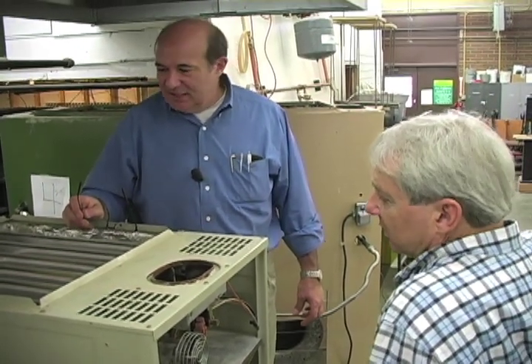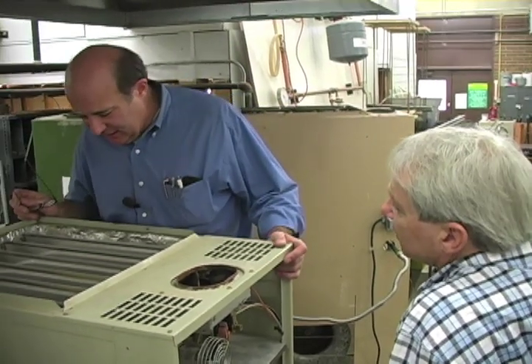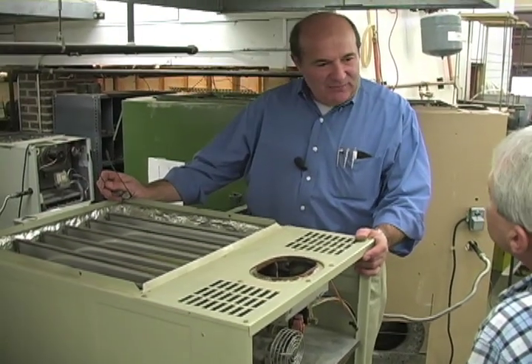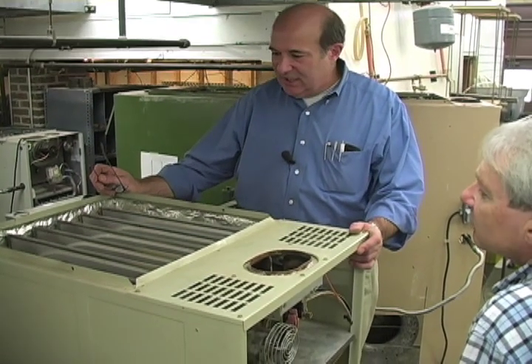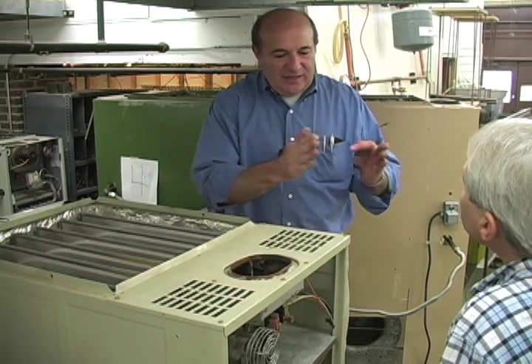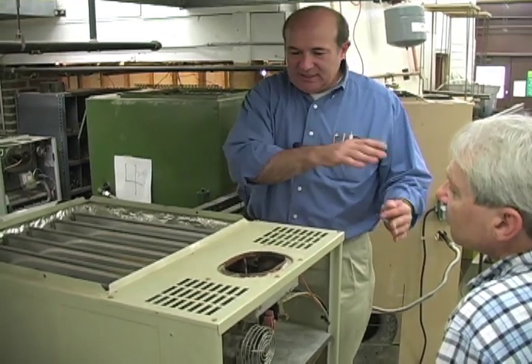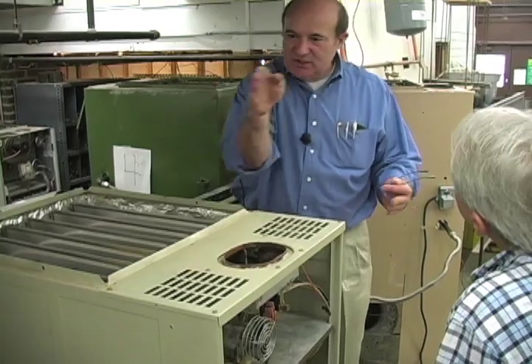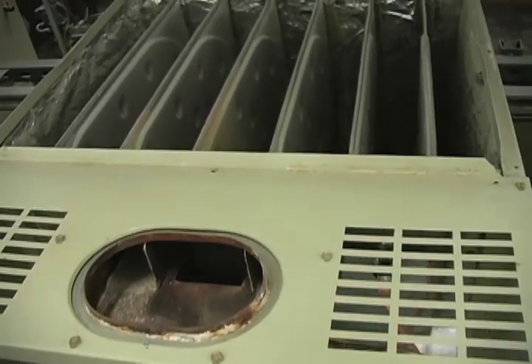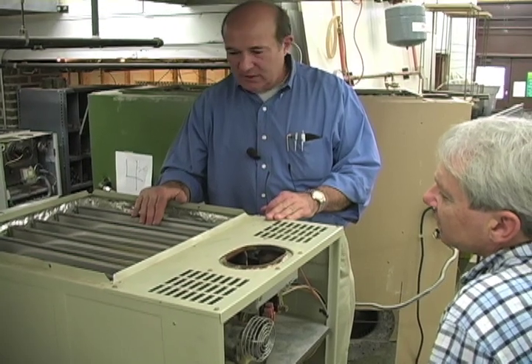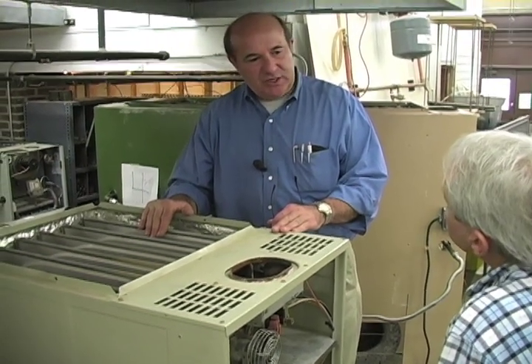Yeah. The last thing I wanted to mention, if we have the time here, is on this heat exchanger in this unit. Again, 85% versus the old 65%. The heat exchangers on these units are much flatter, and they bring a serpentine motion so that the gas comes in the bottom and rises through a series of channels back and forth. That has the capability of holding the heated gas inside that furnace for a longer period, so that we can get more heat exchange to the air over on that heat exchanger. So you'll see a serpentine type heat exchanger on these 80% plus furnaces.